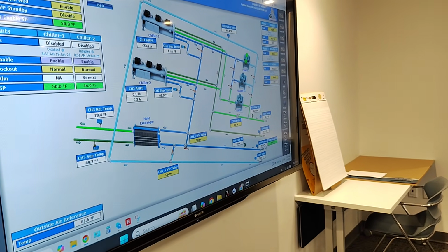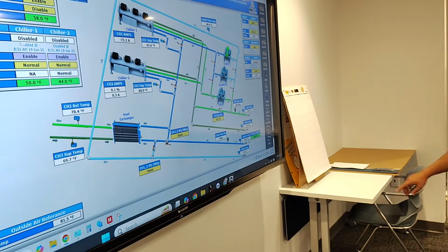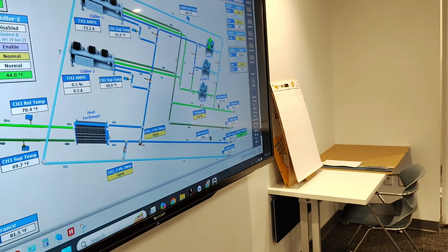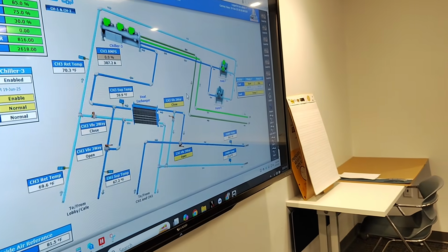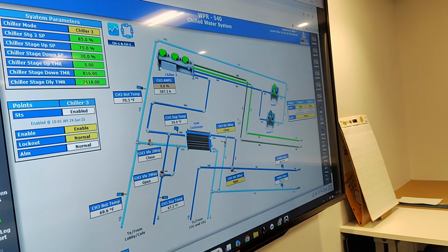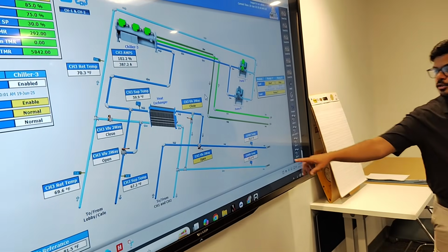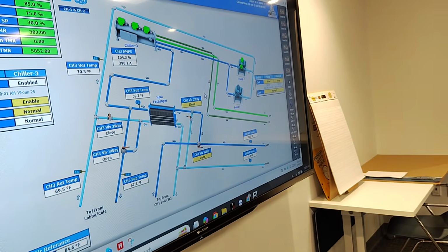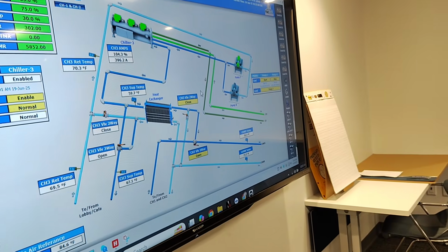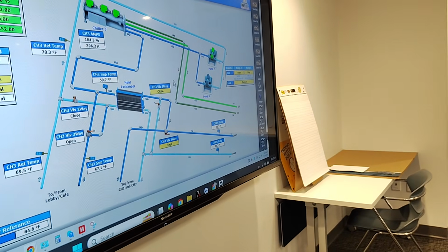That's the chiller temperature. So is this chiller 3, 70.4? Or is this just chiller 1 and 2? No, 1 and 2. Oh, chiller 3. Chiller 1 and 2 are not working right now. Chiller 3 is decommissioned. So that's your chilled water supply temperature set. So you're saying, what's the temperature leaving the chiller going into that heat exchanger?